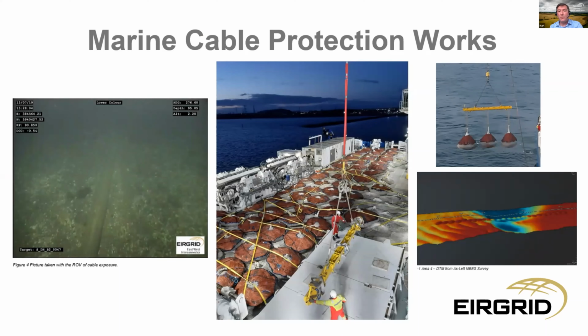Whilst the majority of the route was fine and our existing protection remained unchanged, in this picture here, you can see a cable exposure was identified. The team conducted a cable integrity risk assessment and assessed this and any other potential areas of concern. Remedial works were carried out using NKT Victoria in late 2020, where we installed precise rock placement bags over specific locations of the EWIC HVDC cables.